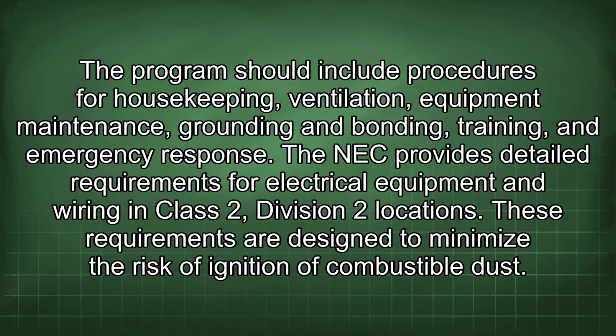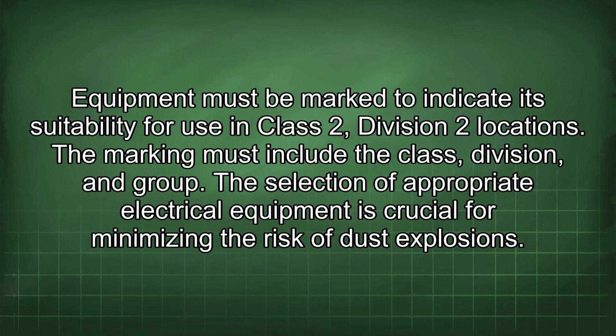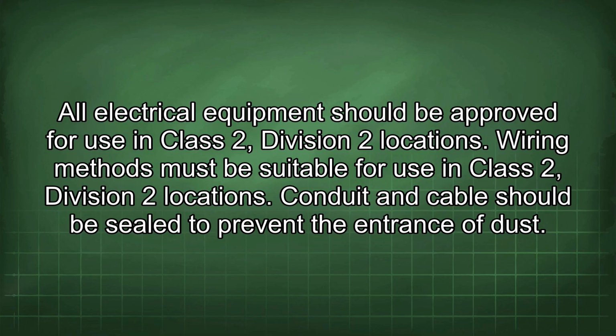The NEC provides detailed requirements for electrical equipment and wiring in Class 2, Division 2 locations. These requirements are designed to minimize the risk of ignition of combustible dust. Equipment must be marked to indicate its suitability for use in Class 2, Division 2 locations. The marking must include the class, division, and group. The selection of appropriate electrical equipment is crucial for minimizing the risk of dust explosions. All electrical equipment should be approved for use in Class 2, Division 2 locations.